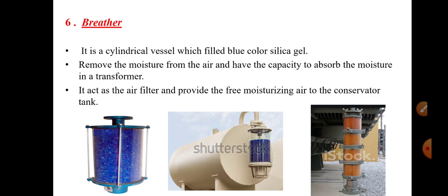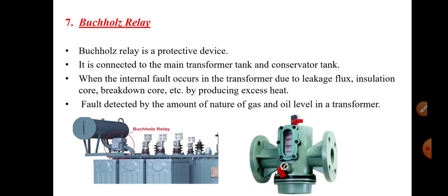The next part is the breather. From the figure, we can see it is a cylindrical vessel filled with blue-color silica gel. Sometimes there is moisture present in the conservator tank oil, so to remove this moisture the breather is used. It acts as an air filter and provides moisture-free air to the conservator tank.